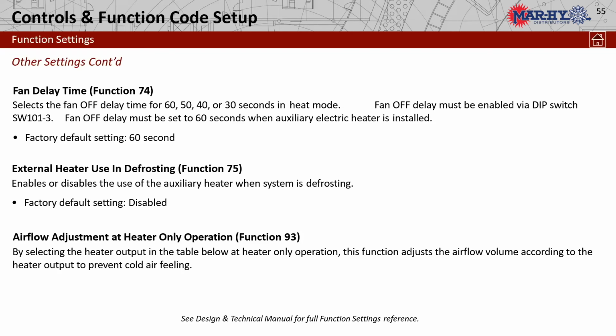But now if you don't have strip heat, because these things do perform pretty well, between down to 5 degrees, we only lose a few thousand BTUs. And if you choose not to use strip heat, when this unit goes into defrost, it'll do just like the mini splits. It'll shut down the indoor fan until the defrost is complete. It'll reheat the coil, and then the fan function will start up again. Very similar to what we do with the minis already.